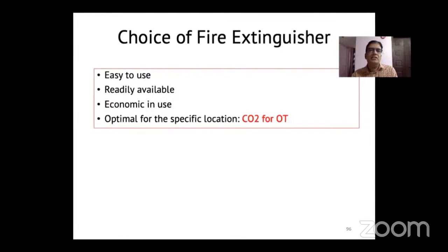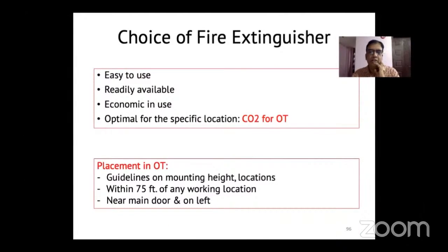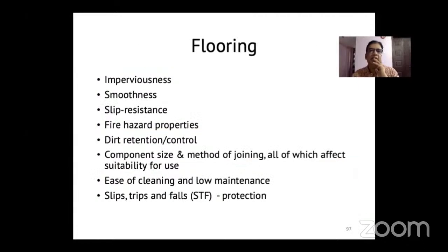Choice of fire extinguisher, normally there are different types which are available, the powdered ones, the carbon dioxide one and other things. But carbon dioxide is the most optimal for operation theatre because it is readily available and economic to use. And it is not harmful to the patient in the event of an intraoperative fire. Where should it be kept? It is normally kept within 75 feet of any working location, near the main door and on the left.